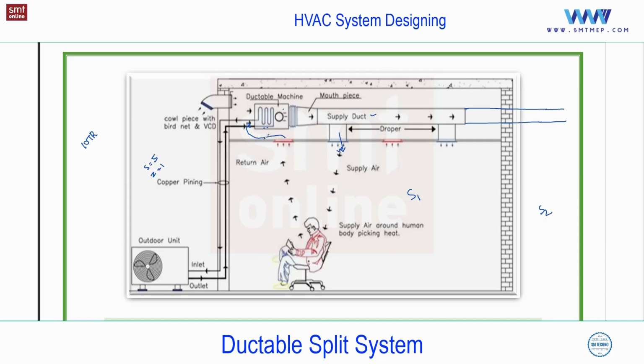Because the controlling is 1. So if all the spaces have the same timing and temperature, we can connect them with a single unit. If you want multi-zoning, we have alternate options with a CAV or with a VRF, etc. That we'll discuss later. At this level, just try to understand the concept of the ductable split. So here we can attach the duct. Second, so the first point is the capacity. Second is the duct.